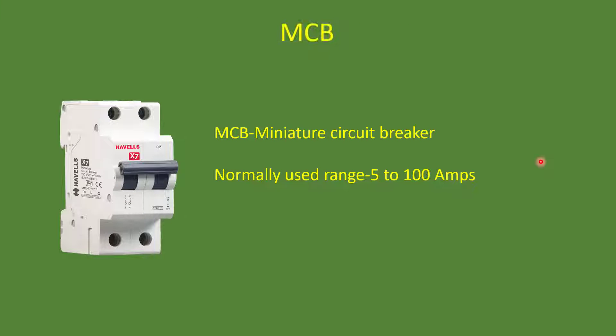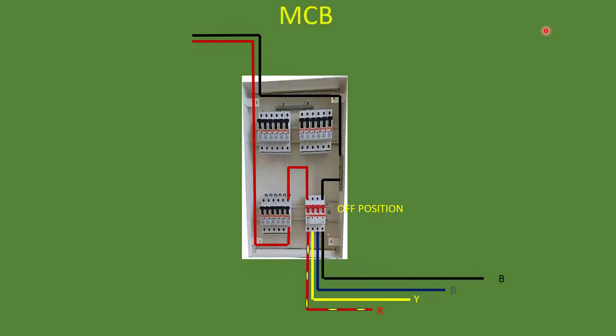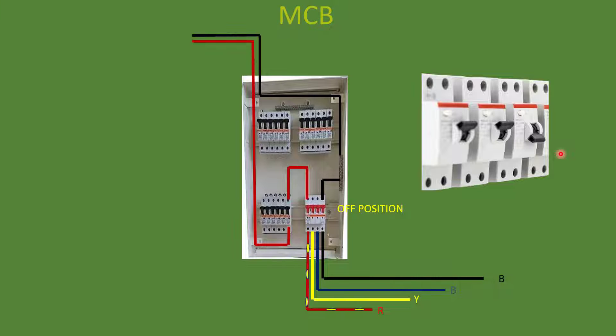The first one is MCB — the full form is Miniature Circuit Breaker. Normally it is used for a current range of 5 to 100 amps. We can see MCBs inside a final distribution board, which is very commonly used everywhere. If the lever is on the down side or bottom position it is in the off position. To turn the MCB on, we need to push the lever upward. This is the on position and you need a slight force to move it from off to on.